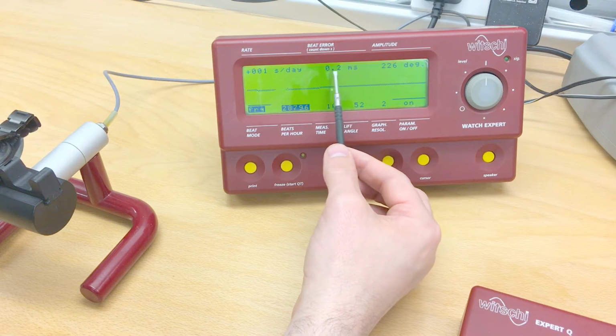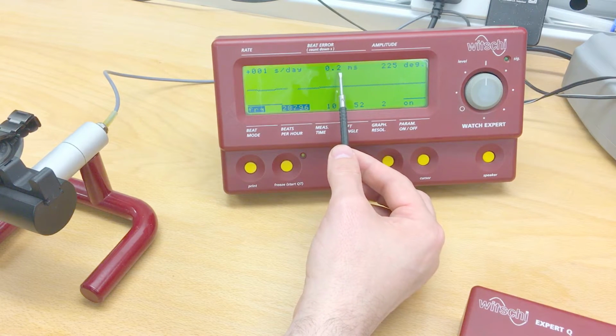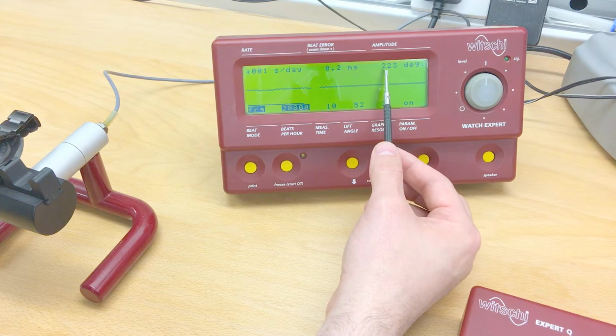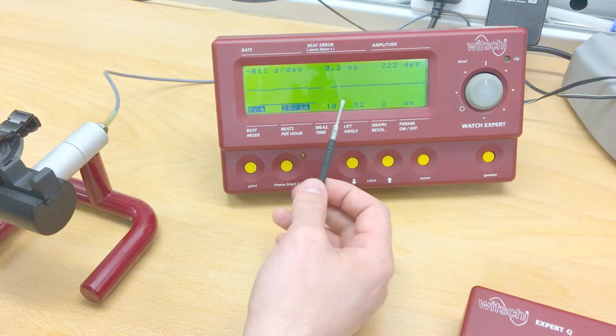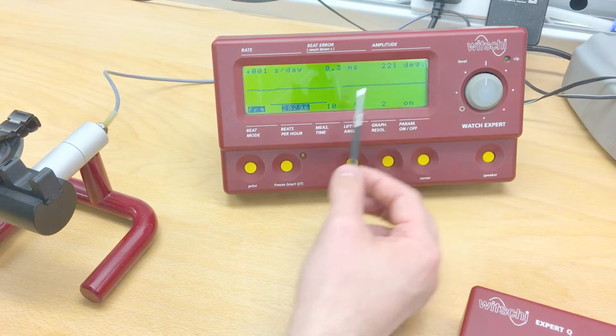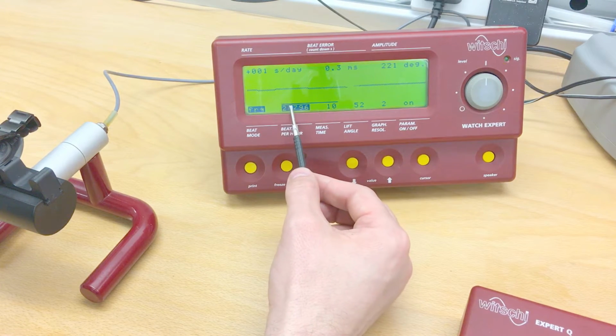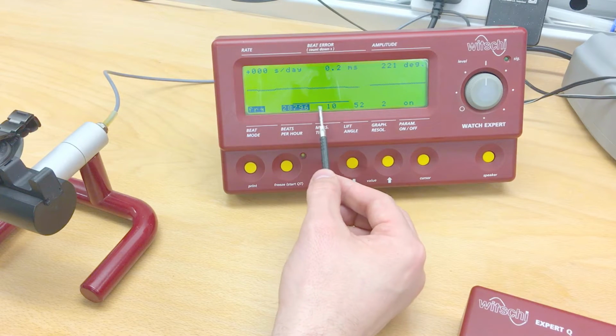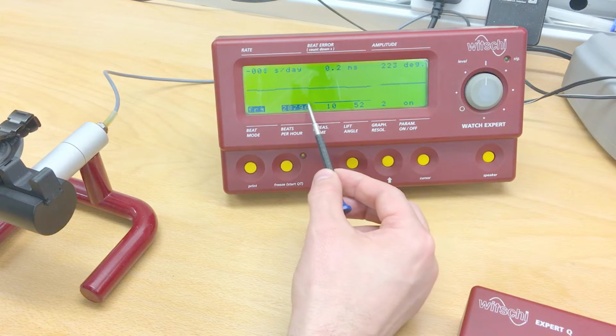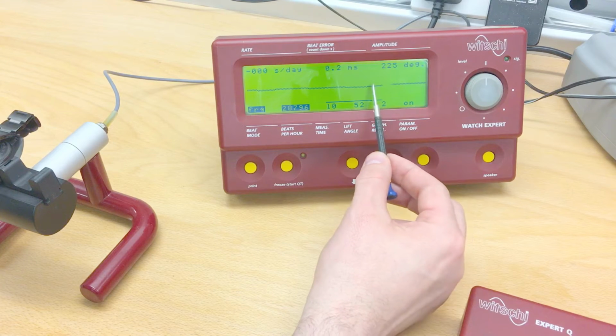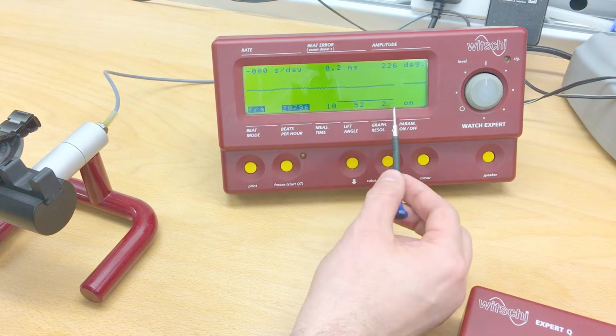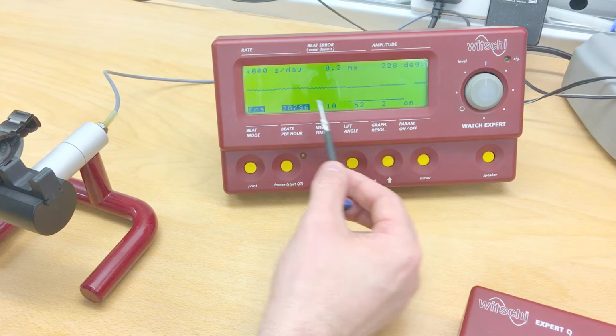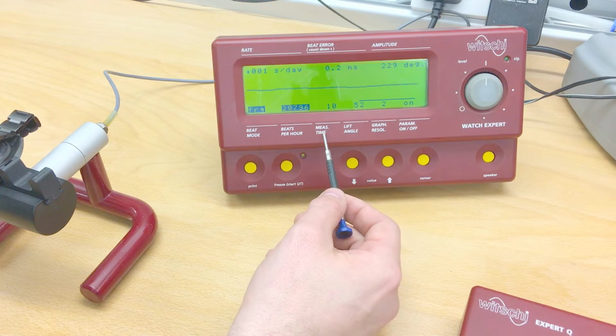The beat error, which is the difference, say, between a tick and a tock: are they identical or are they biased in one direction or another? The amplitude indicates how much the watch is wound. This solid line along here that keeps moving every 2 seconds is the averaging. So it takes that chunk of the graph and gives you an average, and that's what that reading is. That's the measuring time there.